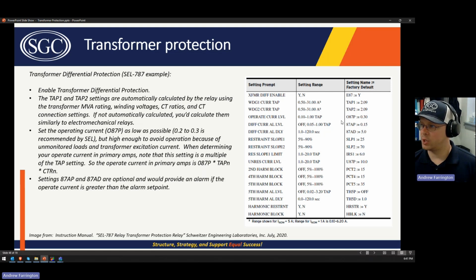Then you set your operate current. That'll be dependent upon the relay manufacturer's recommendations, and also if the transformer has particular recommendations. Sometimes they may say the operate current for a three-legged core transformer is different than the recommended operate current setting for a four-legged core transformer. Look at your relay manual. The 787 relay manual says that you should set it as low as possible, in about the 0.2 to 0.3 range. That's a per unit setting.